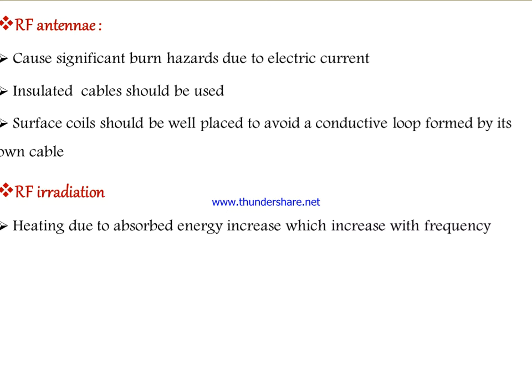Then the RF antenna. To avoid significant burn hazard due to electric current, insulated cables should be used. Surface coil should be well placed to avoid a conductive loop. With RF irradiation, heating due to absorbed energy increases with frequency.